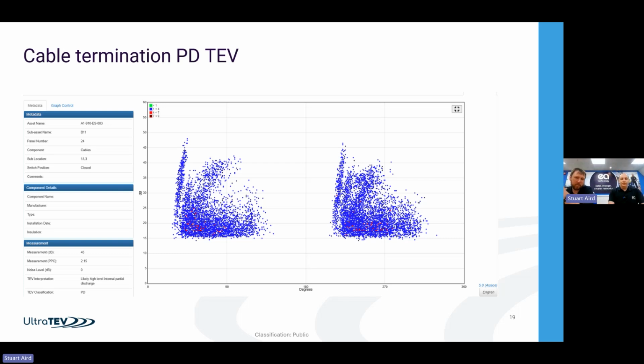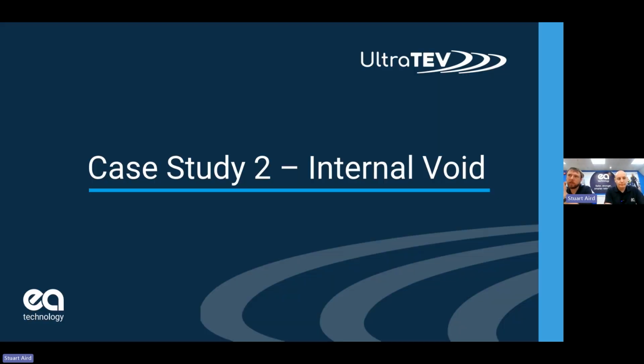Brilliant, thank you, Stuart. So I think just to highlight, that's cable PD location: a 10-second reading with the clip-on CT around the earth strap, press record on a handheld device, and we're getting all the way to cable mapping with distance to fault. That's not something that was achievable even 18 months or 2 years ago. You turned up to site with a laptop and another piece of kit for any provider. So the device and the software features being added to the analysis, as you're about to see in this next example as well, are really bringing features that were only available on high-end systems, whether it be permanent monitoring or otherwise, to this handheld device.